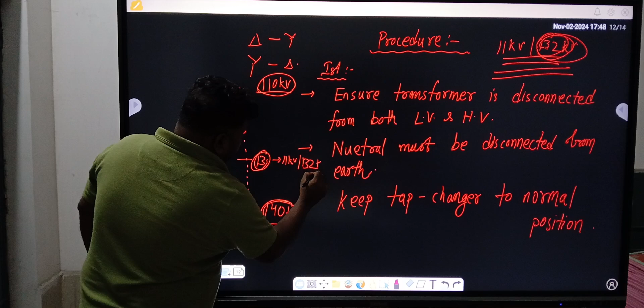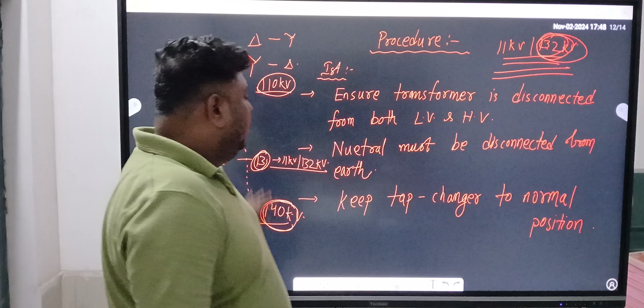Tap number 13 is 11 kV by 132 kV. So this is considered as the normal tapping of the transformer, and we have to keep the tap changer in this normal position before testing. Okay, so these are the ensured conditions before the test.